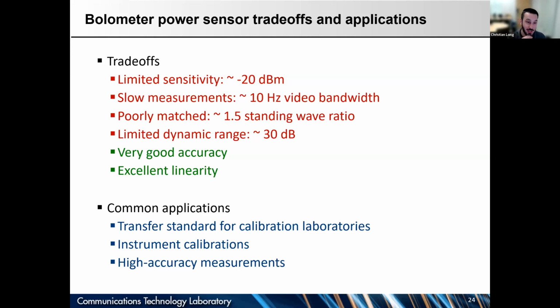So this is a common transfer standard for calibration laboratories and instrument calibrations. And if you want the highest accuracy measurements, this is the kind of power sensor that you might be interested in.